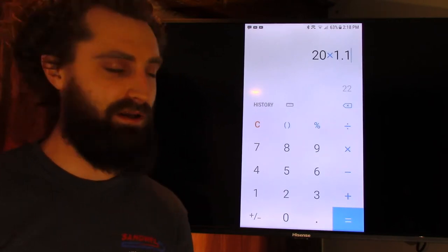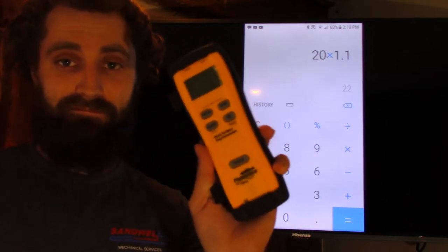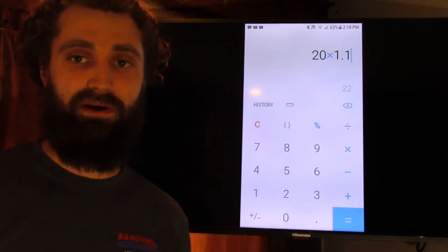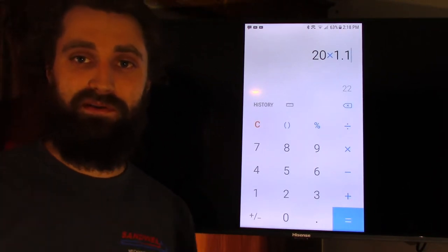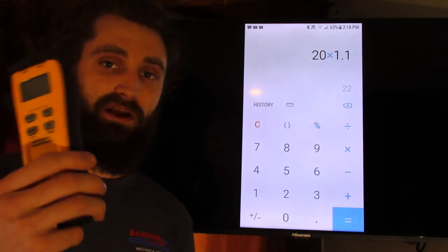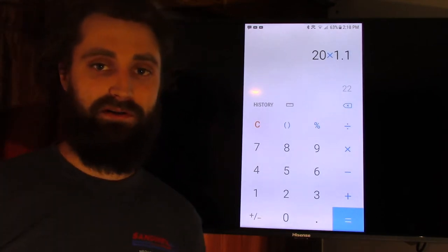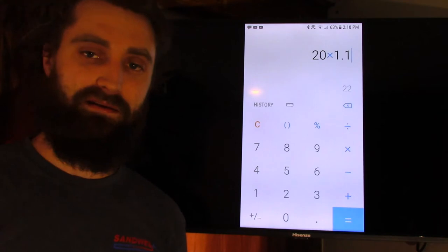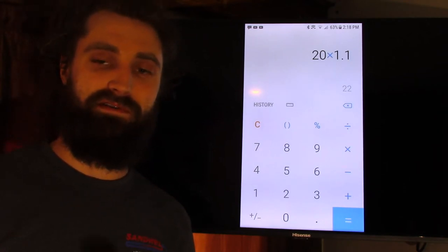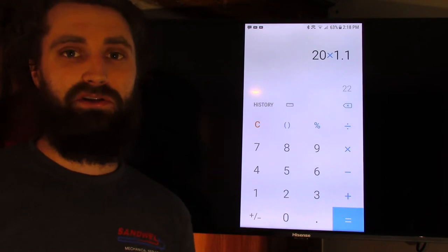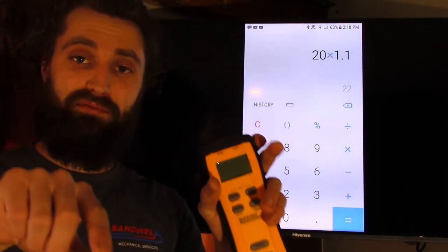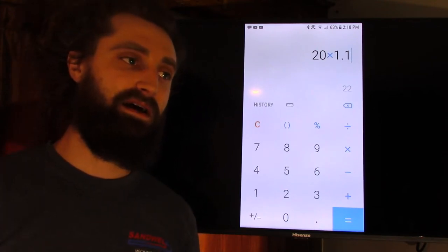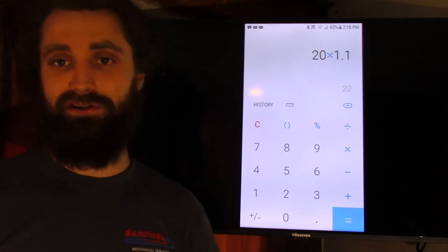4-ton unit, 1600. You're actually measuring the CFM, okay? Because the slightest drop in, or wrong reading will throw this calculation off completely. So go out and get yourself a good anemometer or some way of measuring CFM. I don't care if it's one of those old school vane type of anemometers, or if it's the hot wire anemometer, or I guess you could use static pressure probes, but make sure you have good manufacturer data to go along with that, because without good manufacturer data, you're just kind of shot in the dark, okay?